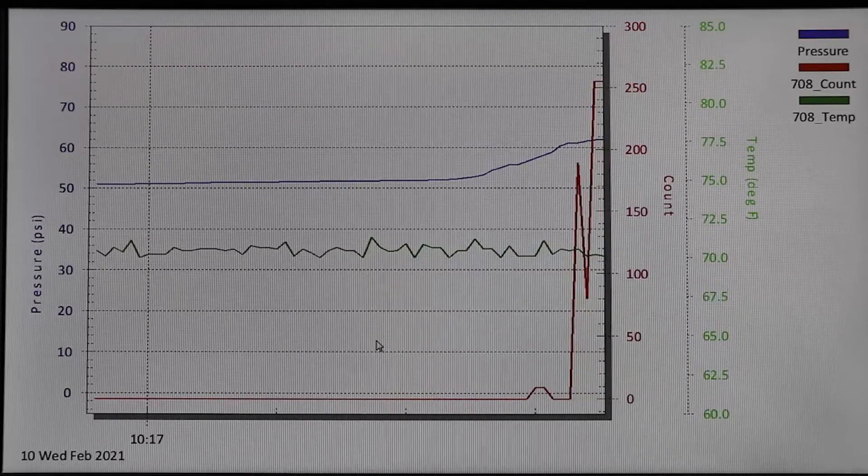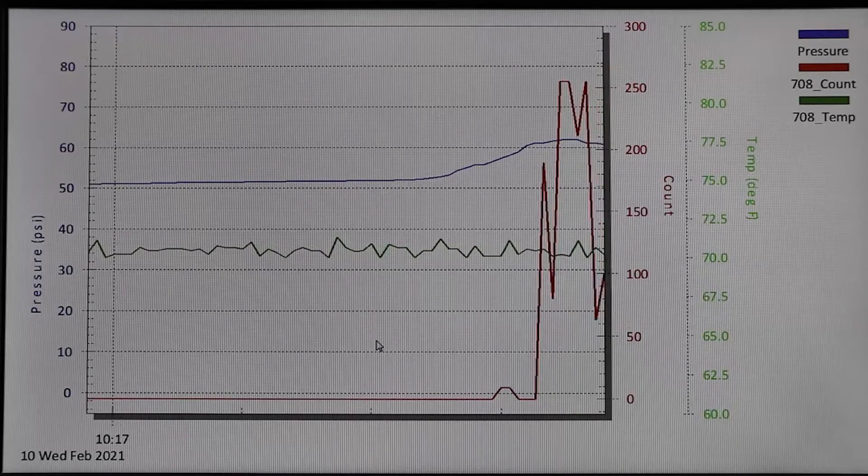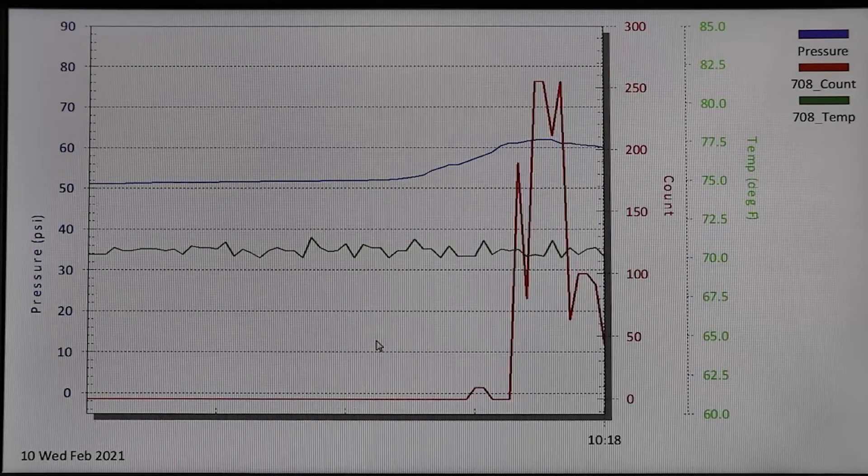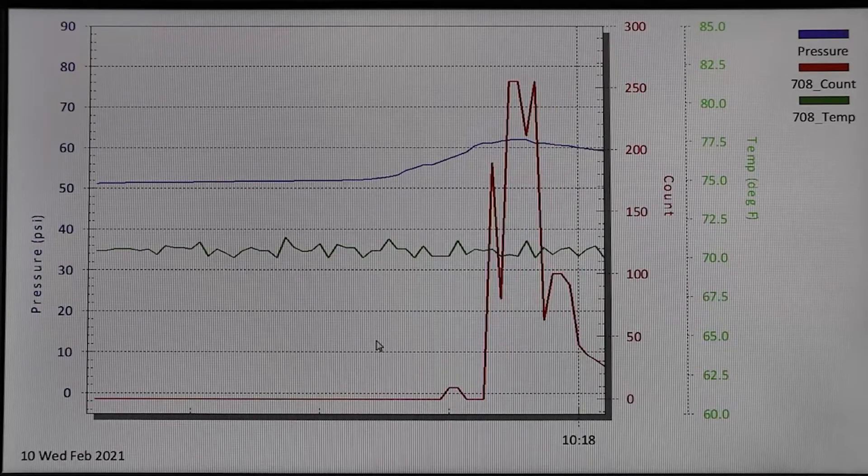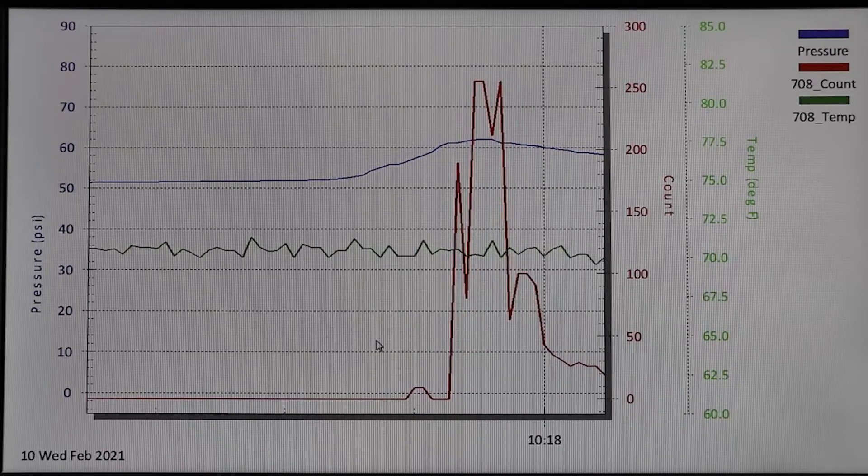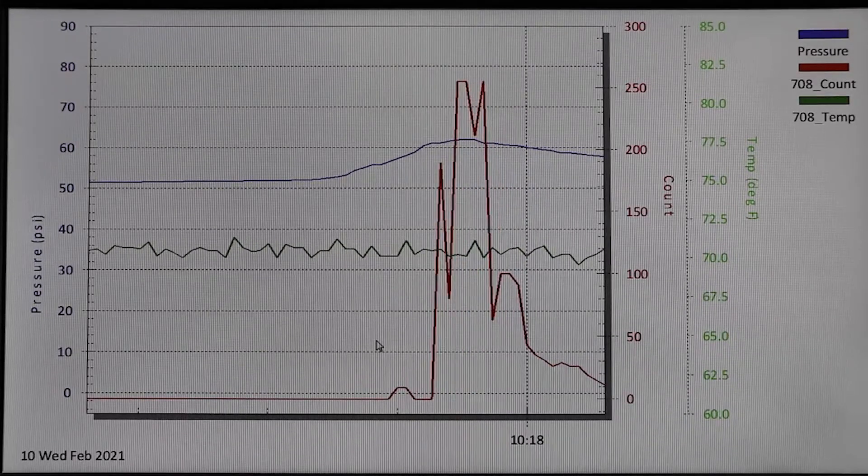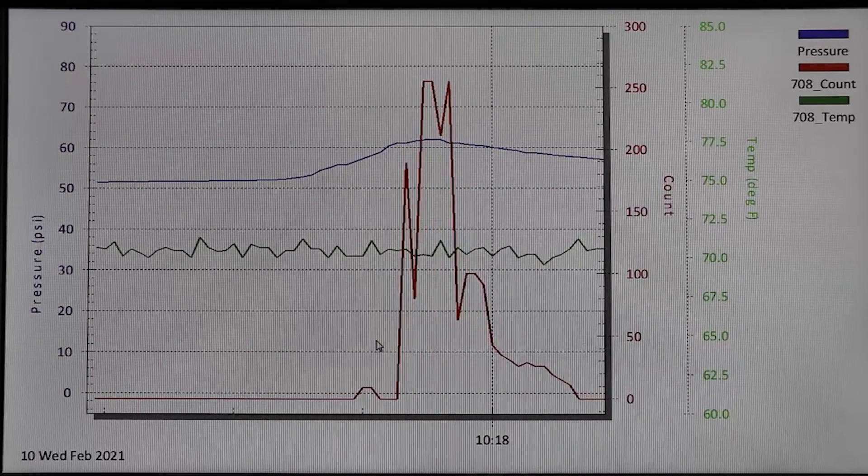Starting at the 10:17 time mark you will begin to see a gradual increase in the system pressure as indicated by the blue line moving up. At this point the pressure is below the relief valve set point of 60 psi and the valve is containing the increased pressure. The valve remains closed and is indicated by the zero data count in red from the acoustic transmitter.